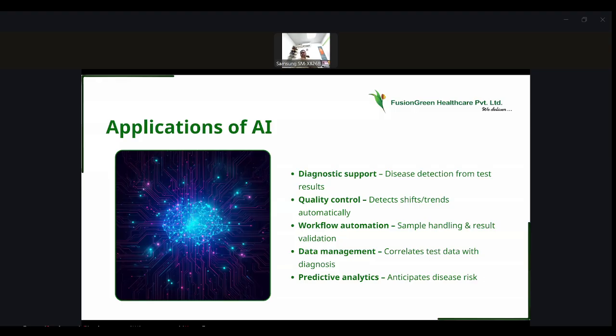Because in diagnostics, when a sample comes, or before starting the experiment, they go for quality control on a daily basis, depending upon the accreditation norms. So they will run 3 levels of QC in the instrument in the morning when they start. Depending upon the level 1, level 2, level 3 QCs and their shifts and trends, the instrument will approve the particular test.